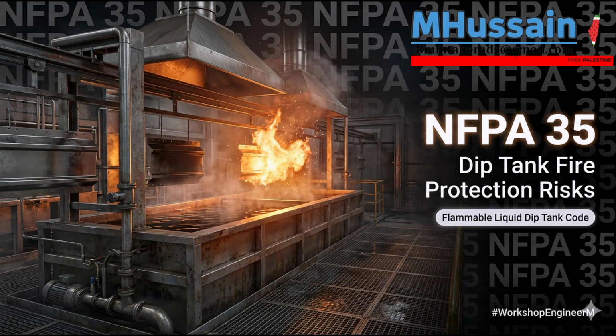It really forces facility owners to audit everything that happens on the floor as a potential ignition source. Everything. The standard even notes in Annex A that operators themselves are massive static generators. The human body is essentially a walking capacitor. The friction of your shoes on the floor or the movement of your clothes generates a charge. Yes, people are a hazard. The standard recommends wearable grounding devices, like conductive footwear or ankle straps, to ensure an operator's personal skin-to-ground resistance doesn't exceed 10 to the 8th power ohms. You literally have to ground the humans.